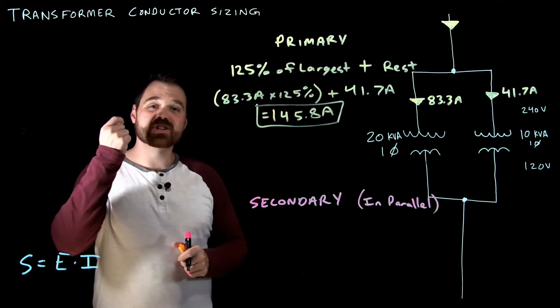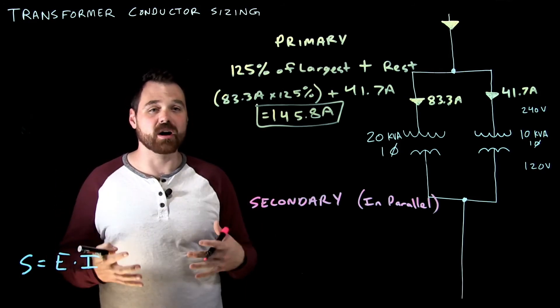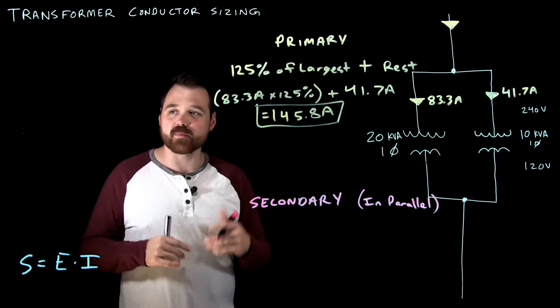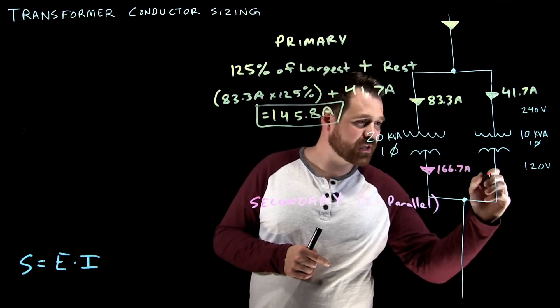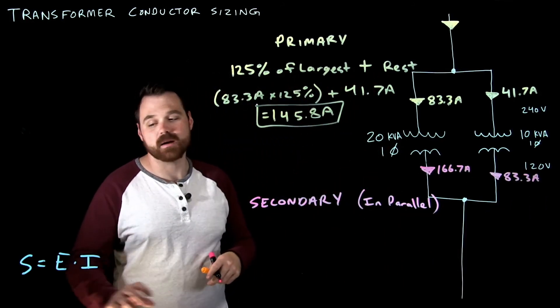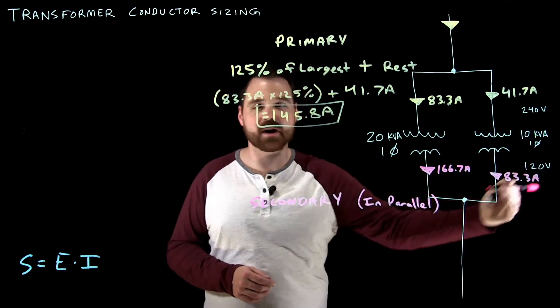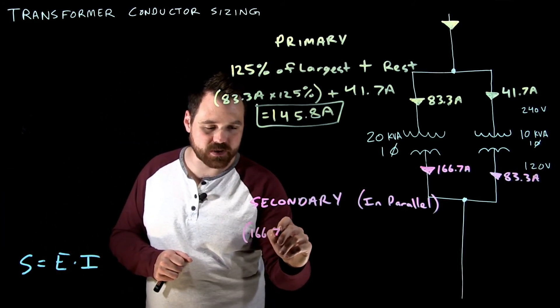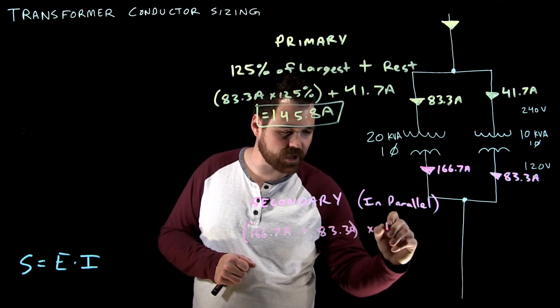What it tells us is it says it is the sum of all of the rated currents times 125%. This is 125% the sum of all the rated currents. So pretty straightforward. I'm going to figure out my rated currents based upon this formula. So my rated currents, I'm going to get 166.7 amps and 83.3 amps. So again, no root three, because we're just single phase. I'm just taking, you know, my two for 20 kVA divided by 120 volts, and my 10 kVA divided by 120 volts. So that gives me my rated currents. Now all I do is I add them all up. So 166.7 plus 83.3, and I multiply that by 125%.